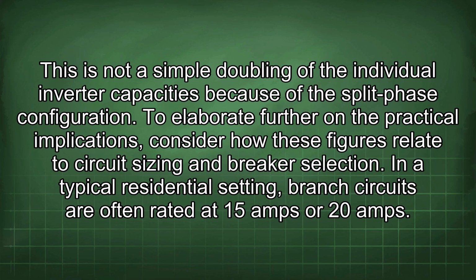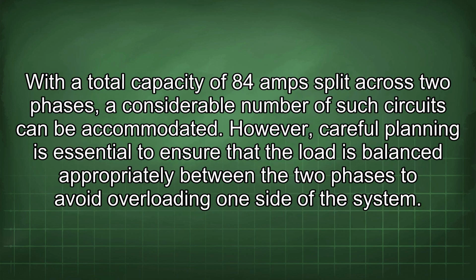To elaborate further on the practical implications, consider how these figures relate to circuit sizing and breaker selection. In a typical residential setting, branch circuits are often rated at 15 amps or 20 amps. With a total capacity of 84 amps split across two phases, a considerable number of such circuits can be accommodated. However, careful planning is essential to ensure that the load is balanced appropriately between the two phases to avoid overloading one side of the system.